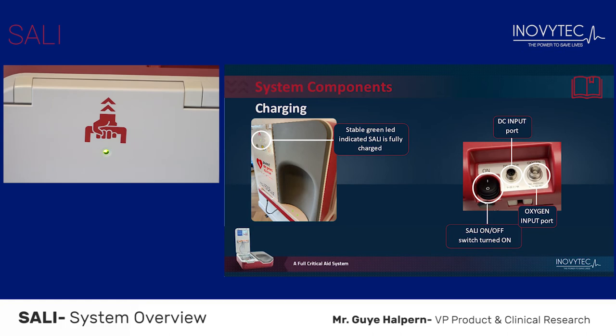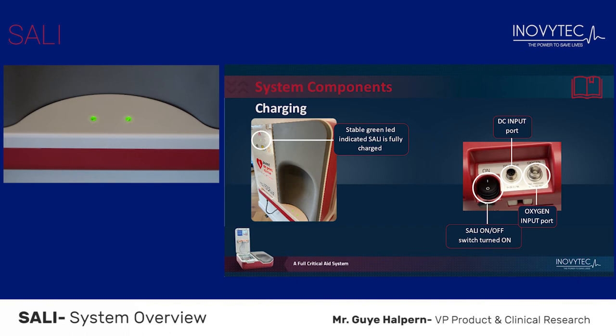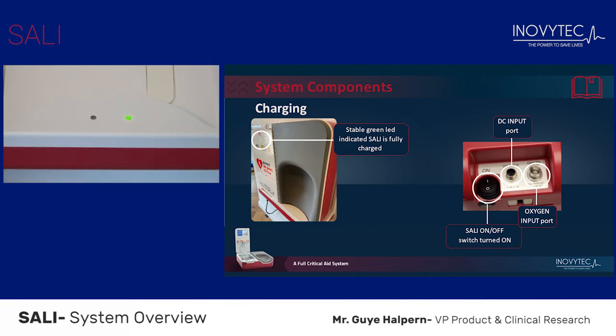A steady green light indicates the unit is fully charged. A blinking green light indicates the unit has more than 50% power and is being charged. A blinking orange light indicates the unit has less than 50% power and is being charged. A blinking red light indicates there is a problem with the connection to the cloud. A steady red light indicates there is a problem with the battery or in the charging protocol.